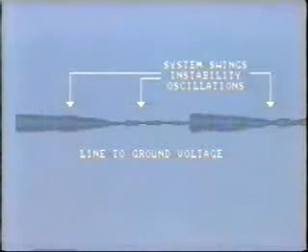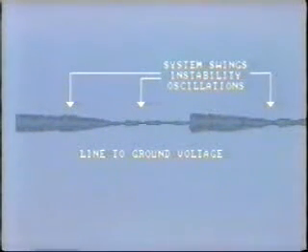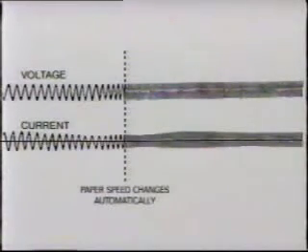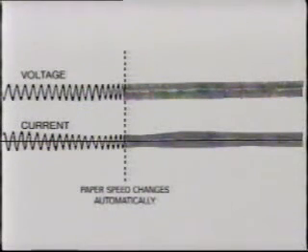We have been looking at oscillograms associated with faults on the system. Generally, the whole story can be shown within a few cycles — usually less than one second. System swings, such as those associated with instability, can also be recorded, but such swings may last for several hundreds of cycles and consequently give us a lot of paper to examine. Some oscillographs have the ability to change paper speed automatically when recording these longer-term swings.